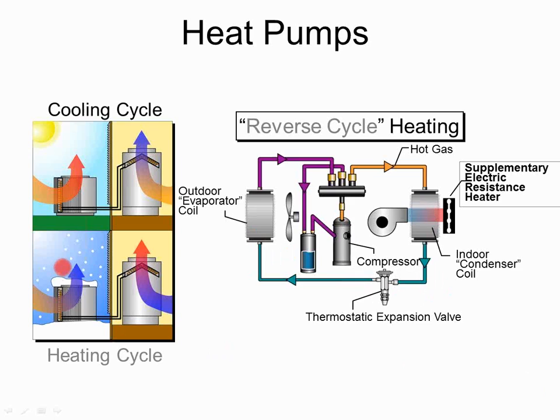With that being said, the colder it gets outside, the harder and harder it is for me to get heat out of the air. Now, there's always some heat in the air, right down to absolute zero, which is like, whatever, minus 273 degrees Celsius or whatever it is. So there's always some heat in the air, but the colder it is, the harder it is for me to get it. And for me to get more of it, I need to either have higher outdoor fan speeds or bigger surface areas of my outdoor coil.